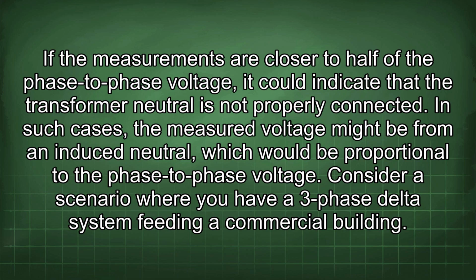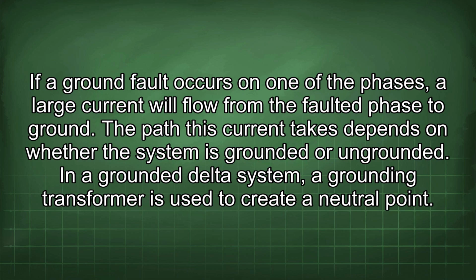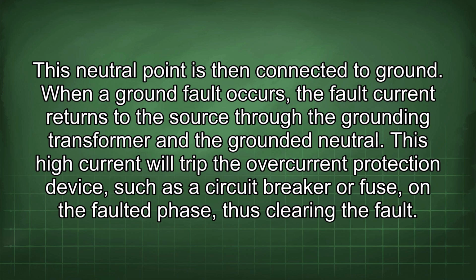Consider a scenario where you have a three-phase delta system feeding a commercial building. If a ground fault occurs on one of the phases, a large current will flow from the faulted phase to ground. The path this current takes depends on whether the system is grounded or ungrounded. In a grounded delta system, a grounding transformer is used to create a neutral point. This neutral point is then connected to ground.